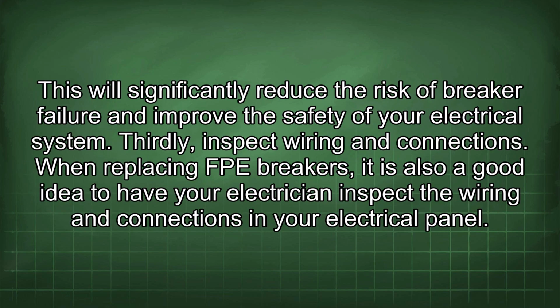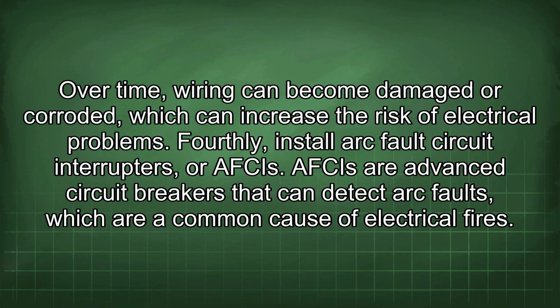This will significantly reduce the risk of breaker failure and improve the safety of your electrical system. Thirdly, inspect wiring and connections. When replacing FPE breakers, it is also a good idea to have your electrician inspect the wiring and connections in your electrical panel. Over time, wiring can become damaged or corroded, which can increase the risk of electrical problems.